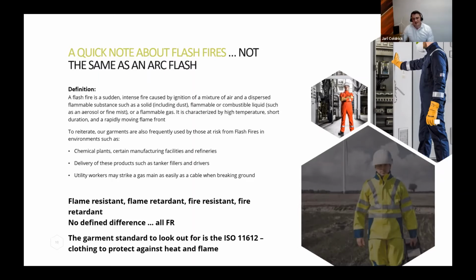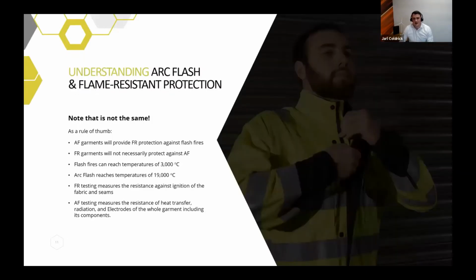So it is essential for the operatives to be protected against flash fire risks, and the relevant standard for that is ISO 11612, which is clothing to protect against heat and flame. But what we must know is that Arc Flash isn't the same as flash fire. Arc Flash protection will provide flame-resistant protection against flash fires, but flame-resistant garments won't necessarily protect against Arc Flash. That's because there's still quite a sheer difference between the two. Flash fire can reach temperatures of 3,000 degrees, and Arc Flash can reach temperatures of 19,000 degrees. There's a significant difference.